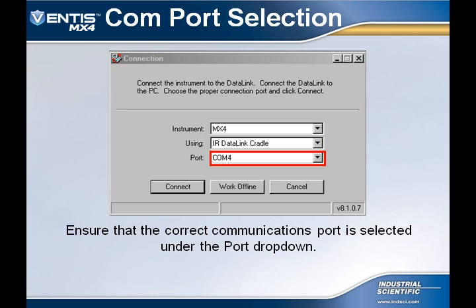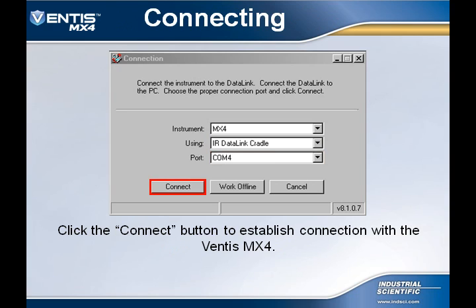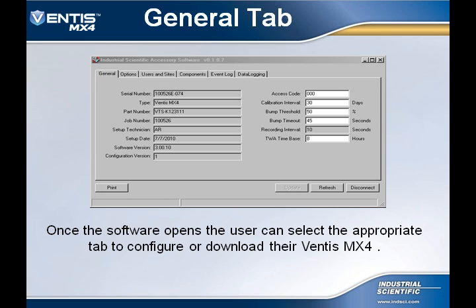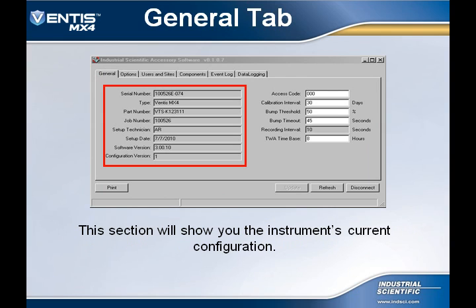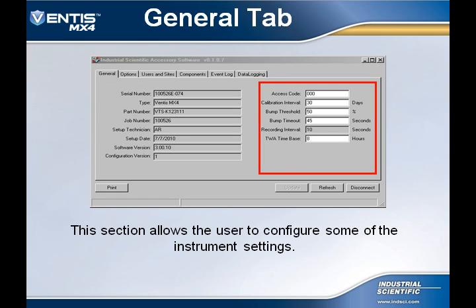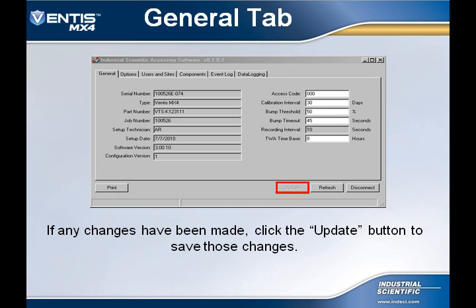Ensure the proper communication port is selected in the drop-down. After the user has ensured that all selections are correct and the Ventis MX4 is inserted in the data link, they can now select the Connect button to establish connection with the Ventis MX4. This is the main screen for the software. The section on the left shows the Ventis MX4 current configuration, and the section on the right allows the user to change options such as calibration interval and configuration access code. If any changes were made, be sure to select the Update button to save those changes.